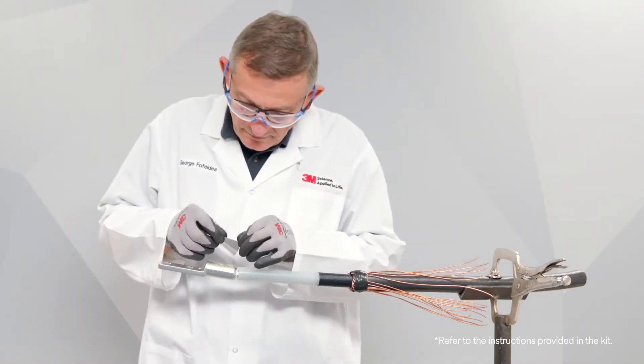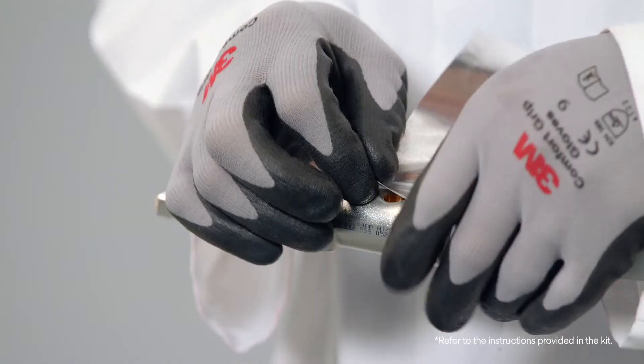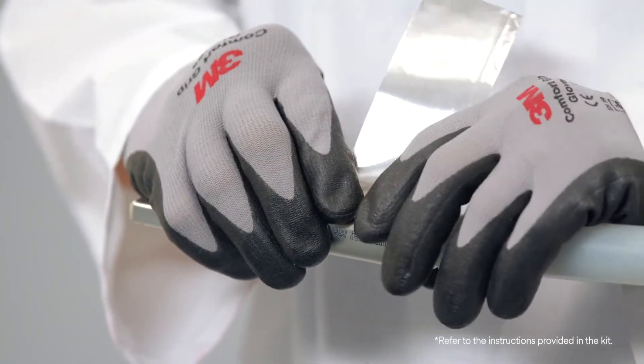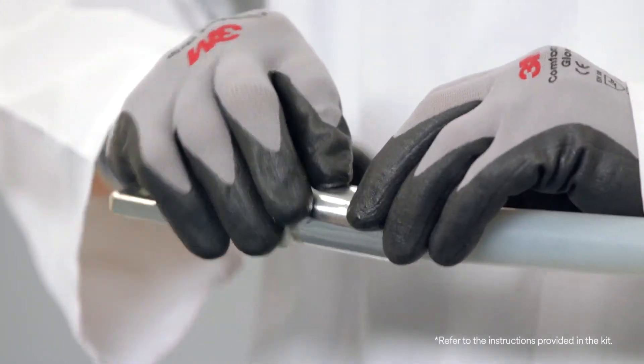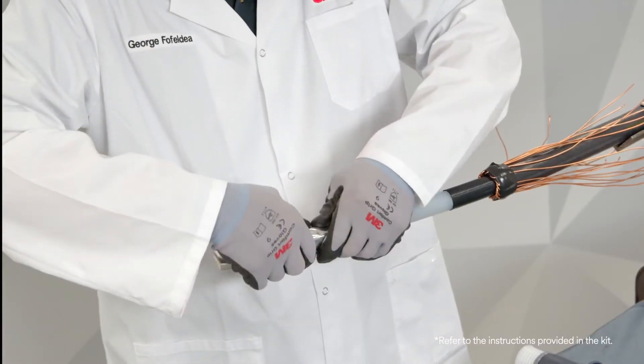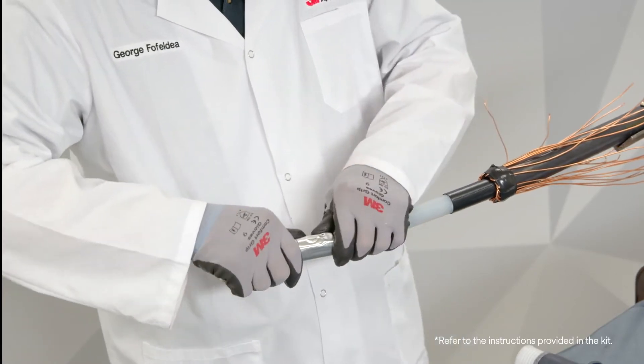After the solvent is dried, apply the 3M Aluminum Foil Tape around the lug until it covers the bolt wells with a second layer. Press down the ends of 3M Aluminum Foil Tape at the final edge and near the lug tapers.